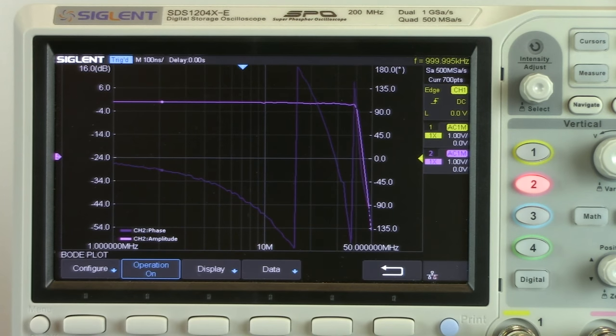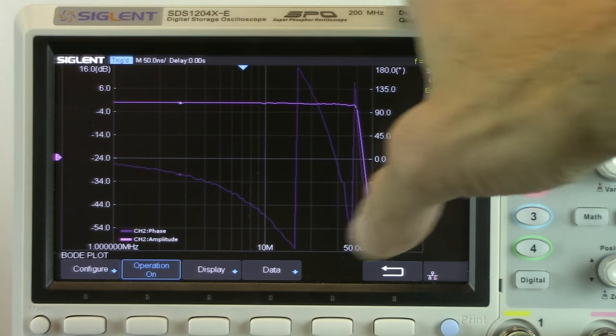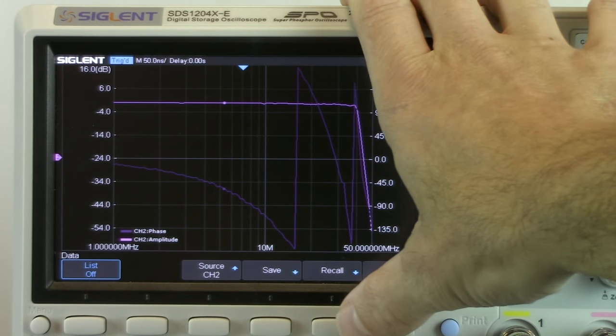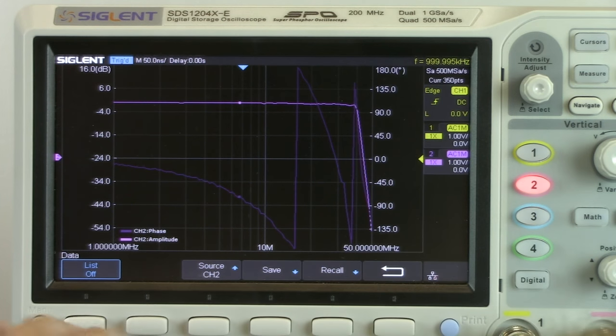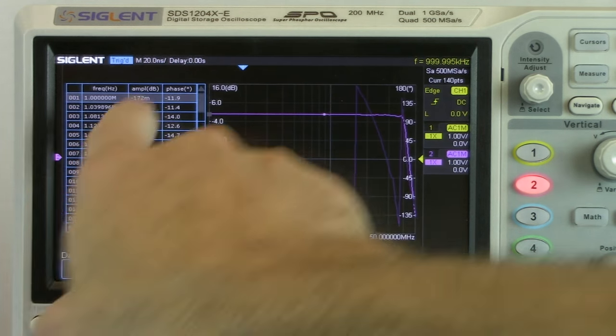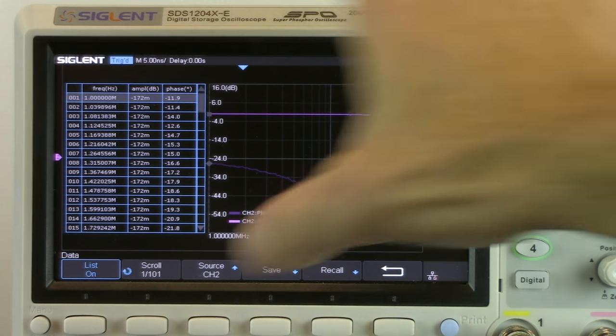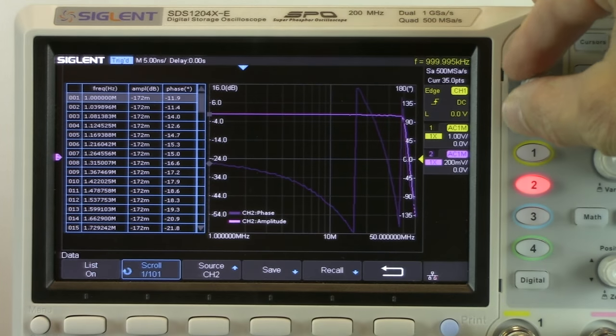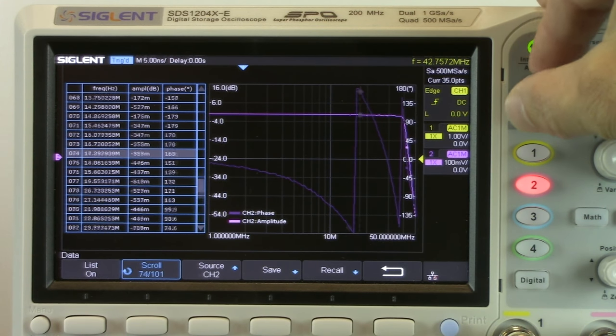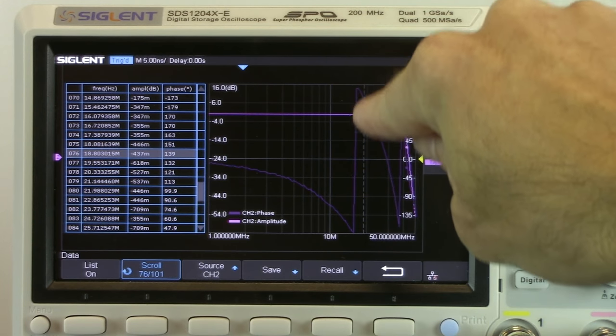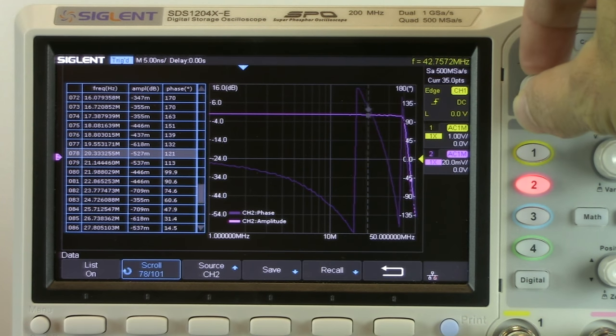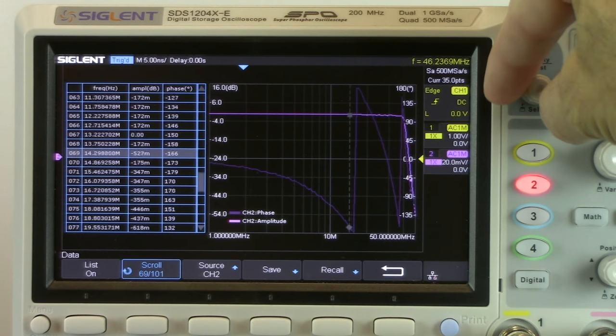We can also take a closer look at the data. So we can go over to data and we can go to list. The list is going to give us a full list of all of the values that we've collected. So it has the frequency, it has the amplitude, and it has the phase measurement at each one of those individual points. We can select scroll and then we can scroll through each individual line and each individual value. And you can see that the point that we're looking at is indicated by these gray cursors in both the amplitude and the phase scale.